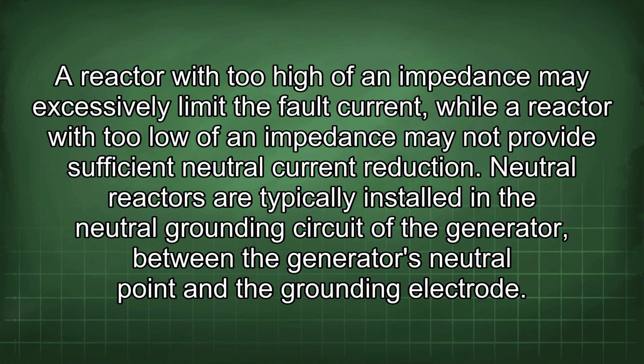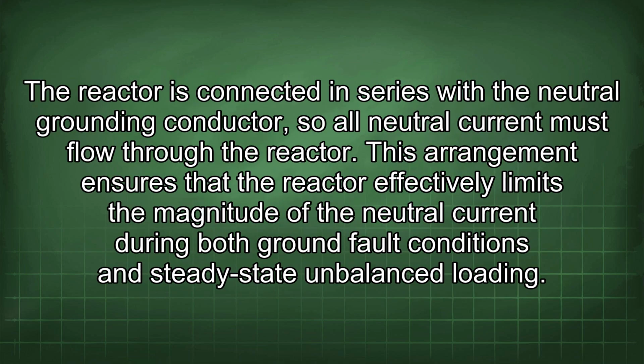A reactor with too high of an impedance may excessively limit the fault current, while a reactor with too low of an impedance may not provide sufficient neutral current reduction. Neutral reactors are typically installed in the neutral grounding circuit of the generator, between the generator's neutral point and the grounding electrode. The reactor is connected in series with the neutral grounding conductor, so all neutral current must flow through the reactor. This arrangement ensures that the reactor effectively limits the magnitude of the neutral current during both ground fault conditions and steady-state imbalanced loading.